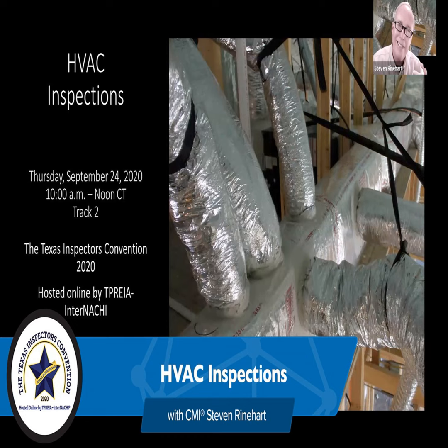I see one of these, one of the first things to do, if I'm running it and everything else looks good, I pull the cover off, get it started, and hang my carbon monoxide detector in one of those first registers. Let me know if something other than regular room air is coming out of it. But that's a forced air, natural, atmospheric, not real good. The problems you see, it's kind of like the water heater. Heat just rises up the flue.